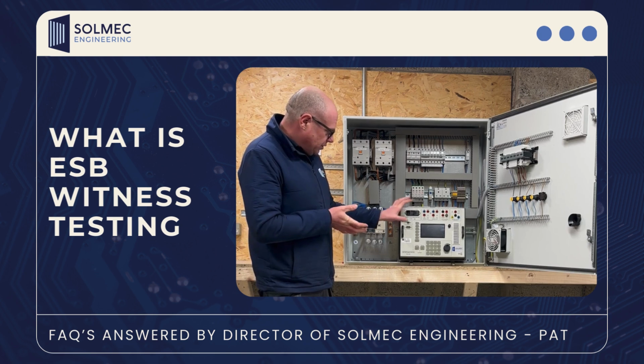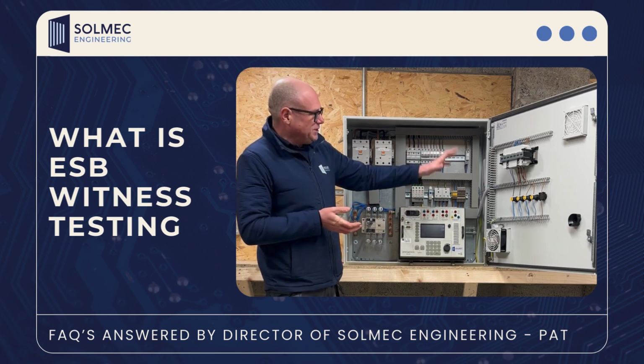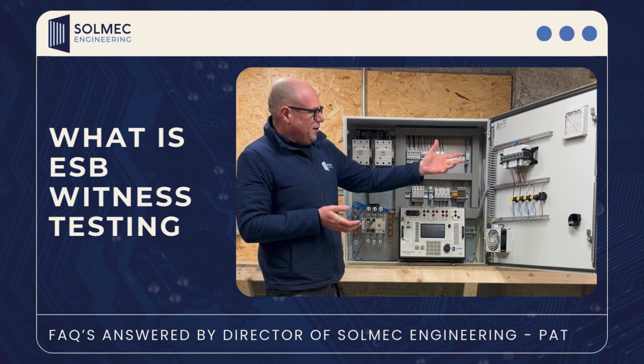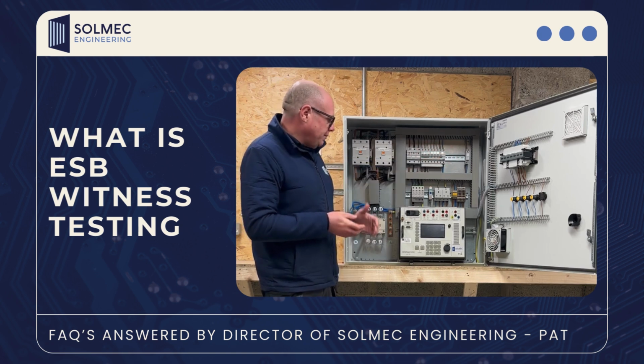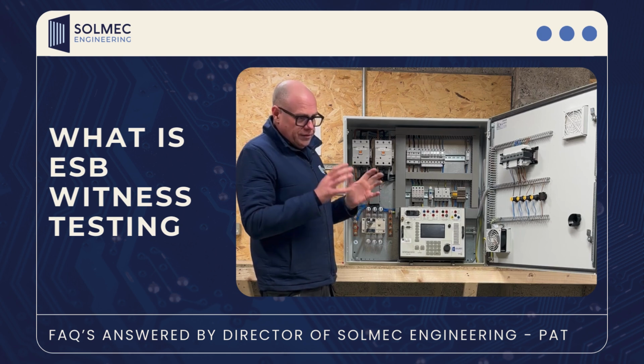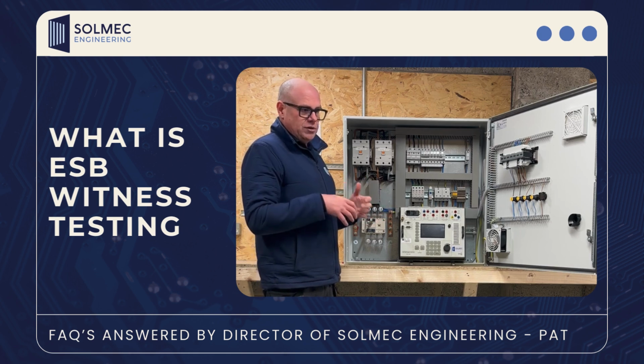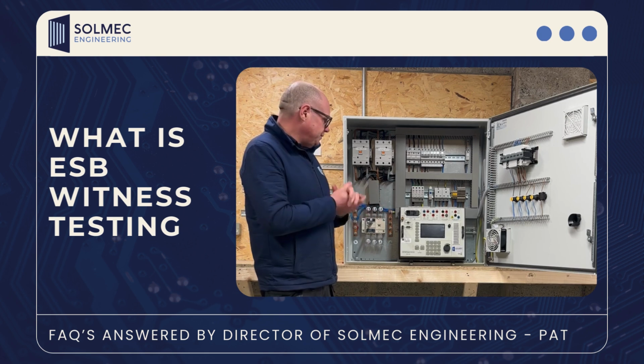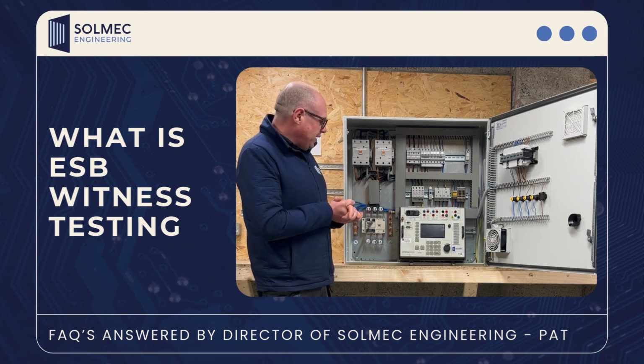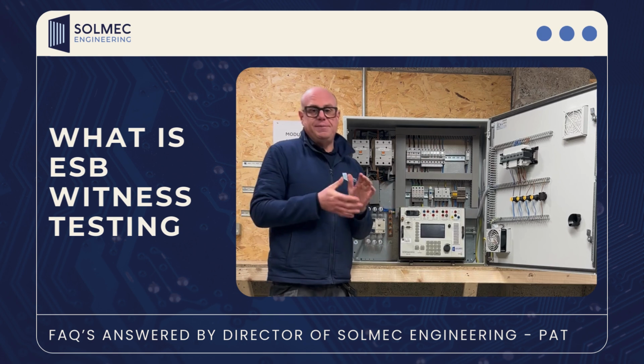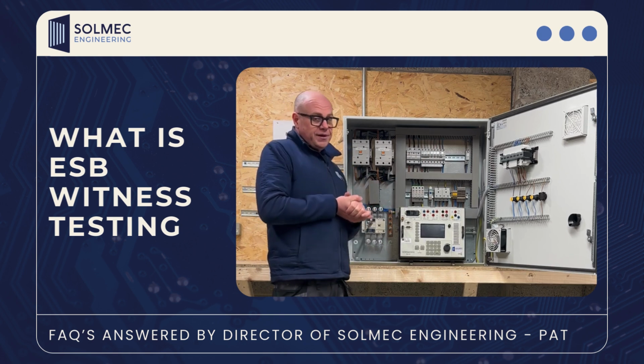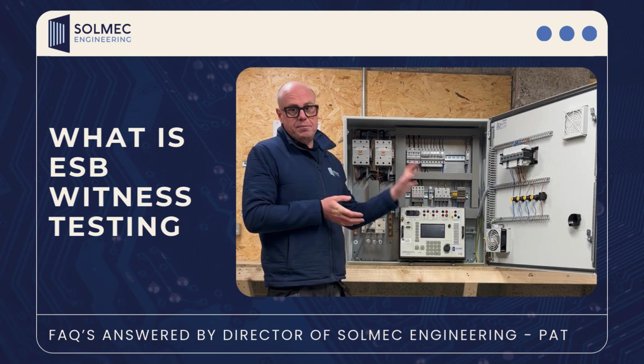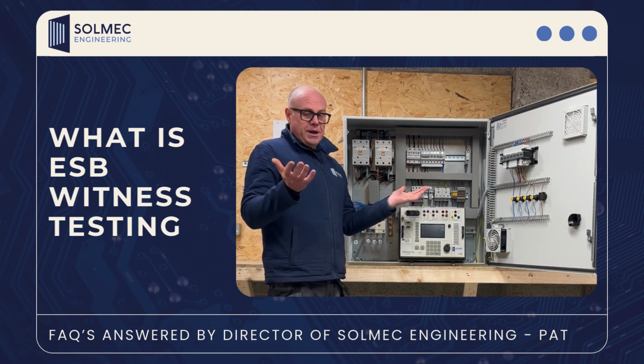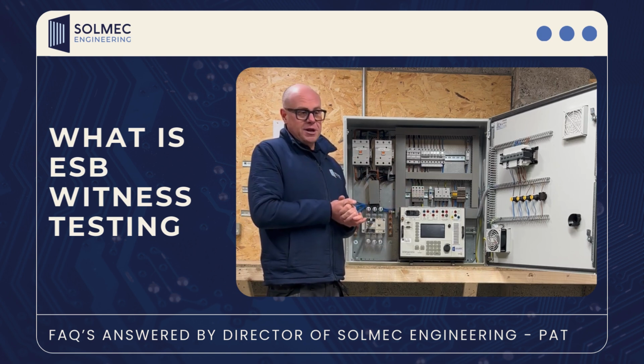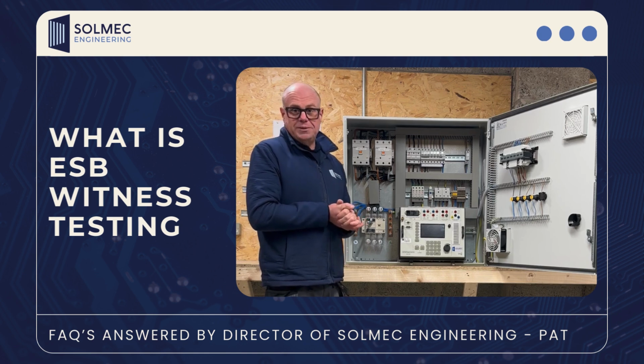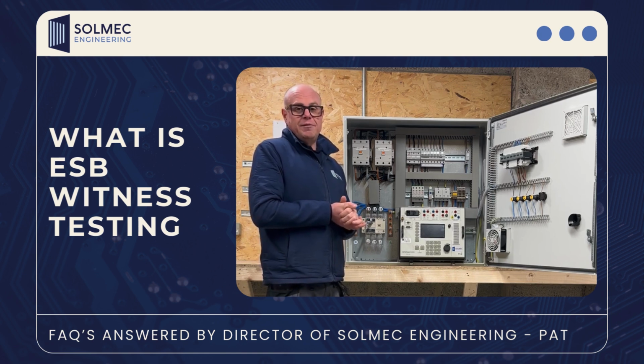It records all timing to make sure that there are time specific trip faults, like it has to be done in a certain time, over a certain voltage, under a certain voltage, over a certain frequency, under a certain frequency. Once we prove all that by doing the test in front of the ESB guy, he will then approve it and say this system is safe and compliant and ready to go. And you can turn on your PV solar system, and your client, who's been waiting a long time, I presume, to get it all up and going, will be a very happy client then.